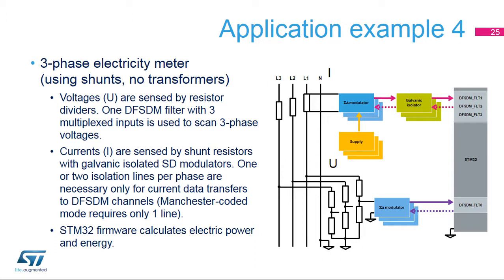Another example shows a three-phase electricity meter design using shunt resistors for sensing current, eliminating the need for expensive current transformers. Voltages are sensed by three resistor dividers and external sigma-delta modulators, and currents are sensed by three shunt resistors, each with one sigma-delta modulator. Because each sigma-delta modulator operates at a high-phase voltage, galvanic isolation is used for data transfers into the DFSDM. If the sigma-delta modulator uses the Manchester-coded serial protocol with an internal clock source, only one isolator per phase is necessary; if it uses the SPI serial format, two isolators per phase are necessary. Each sigma-delta modulator is powered from a separate DC supply voltage.